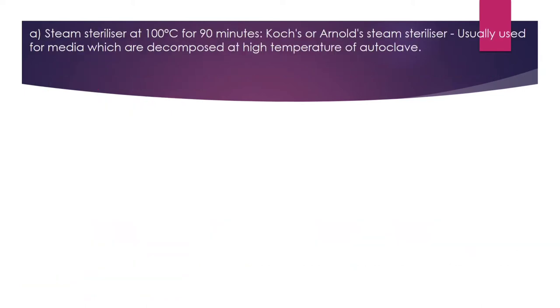The steam sterilizer operates at 100°C for 90 minutes and is used for media that would decompose at the high temperatures of an autoclave.